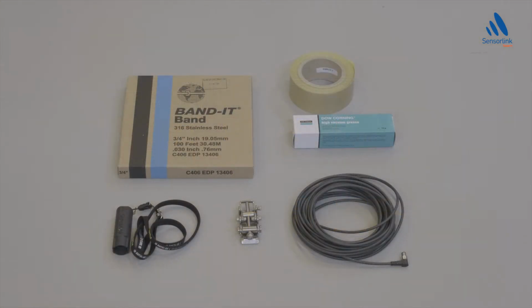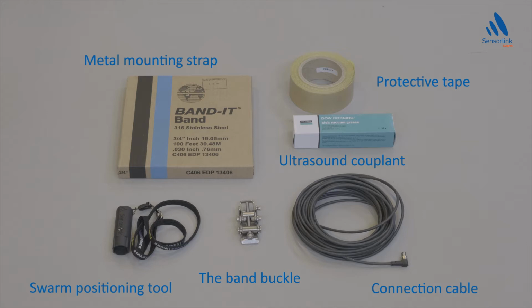This is the installation equipment needed and is sold separately from Sensorlink. Metal mounting strap is used to fasten the bracket to the pipe, and the band buckle is used for tightening and securing. The protective tape ensures galvanic insulation between the pipe and the mounting strap and brackets. More details on how to do this will be shown later in this video. The ultrasound couplant is necessary to ensure acoustic coupling between the ultrasound transducer and the pipe. The swarm positioning tool can be used to adjust the position of the ultrasound transducer if necessary.